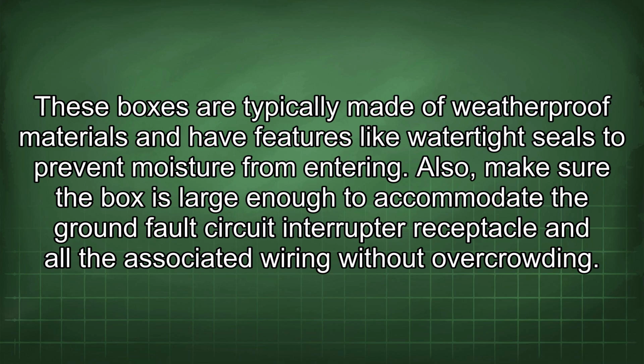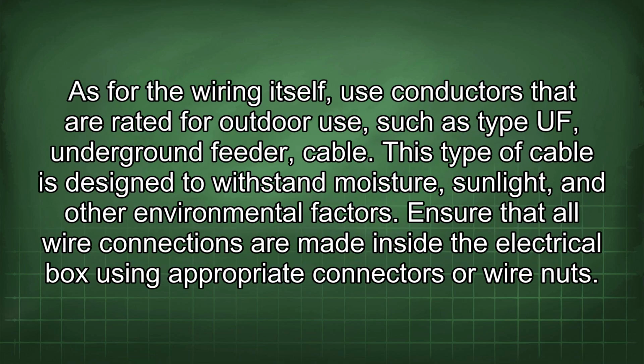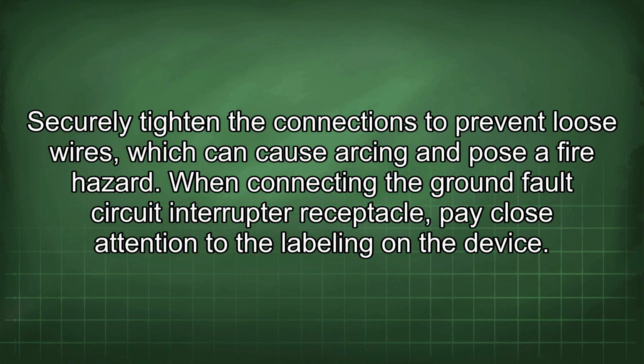wiring without overcrowding. As for the wiring itself, use conductors that are rated for outdoor use, such as Type UF, underground feeder cable. This type of cable is designed to withstand moisture, sunlight, and other environmental factors. Ensure that all wire connections are made inside the electrical box using appropriate connectors or wire nuts. Securely tighten the connections to prevent loose wires, which can cause arcing and pose a fire hazard.